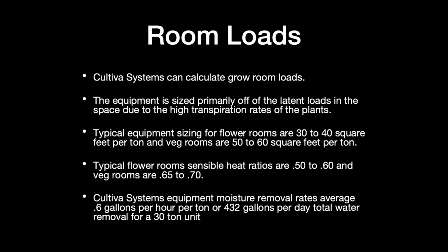Your typical flower rooms, though, this is your sensible heat ratio. This is where you run into issues with trying to do it with standard HVAC equipment. You're looking at SHRs in the 0.5 to 0.60 range. The veg rooms, and this is where in some of our initial jobs, because of cost, people will try to use just standard HVAC equipment, and they're trying to get something in the range of a 0.70 SHR. The issue there is being able to control that equipment to the flatline temperature and humidity conditions that the plants are really requiring.